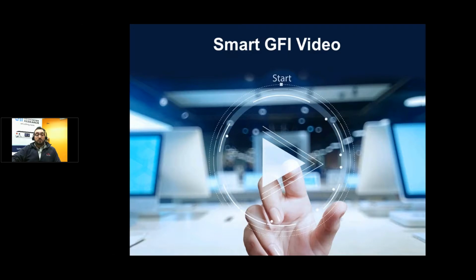If it detects that much current flowing through ground or not returning through the return path, the Smart GFI circuit will result in a failure. Again, this will be different from the Hipot test failure. So make sure you understand the difference between a Hipot failure breakdown versus a Smart GFI failure, because this is more of a user protection circuit, and it doesn't tell much about the device under test, other than that it may be leaking to ground.